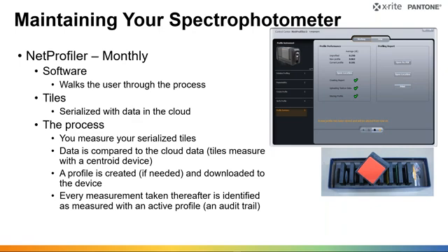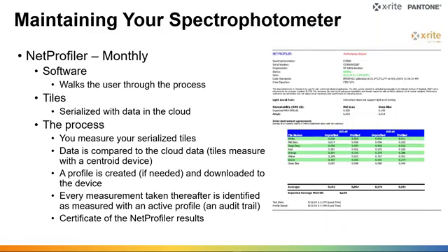Sometimes it reuses the existing profile. Sometimes it generates a new profile. Okay. And then at the end of that, you get a certificate of the Net Profiler results. The certificate's for a different device. And you can see it actually tells you in this table, how far off was it unprofiled on these various color tiles, and where did I go after I applied the profile. So you end up measuring the tiles twice. Once you measure them and it calculates the difference you have, and then it measures them again after it applies this new profile to validate, yes, I improved it in this case from 0.16 to 0.06 delta E. So I've just saved myself in this example essentially 0.1 delta E of error that my instrument would have produced had I not profiled it.